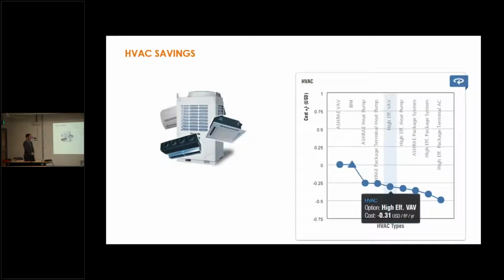The HVAC system modeling in this is a bit, I would say, pretty rough. They're not really modeling every HVAC configuration. They're using much more simplified COP values for their energy efficiency values and such. So they're not doing a thorough energy analysis with regards to the HVAC system, but this platform does allow you to take the models that you're generating in Insight 360 and export them to things like DOE2 or EnergyPlus, and pick up those models and start manipulating them yourself if you have more thorough things to study. And we could quantify things like HVAC systems.